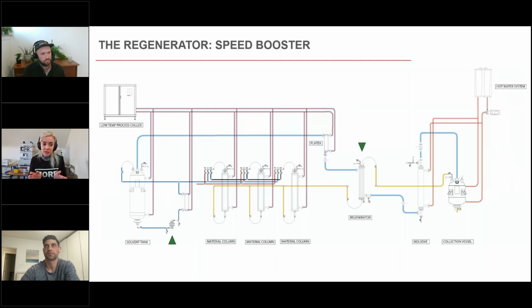Plate exchangers can be mounted to the walls, which I also love. You can take advantage of gravity, heat going up and cold coming down, and you can make an even weak chiller much more effective by taking advantage of the proper heat exchanger. Coils are super prone to clogs, and a plate exchanger is just not going to have those same issues because it's a tremendous amount of surface area, but it's a lot more free-flowing inside compared to that narrow tube, which is a huge advantage.